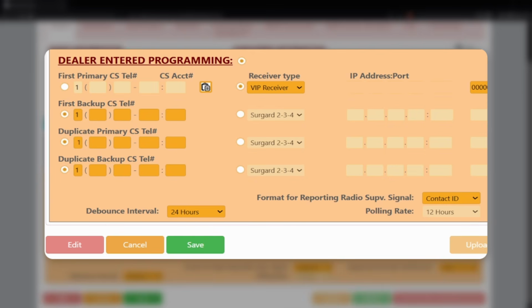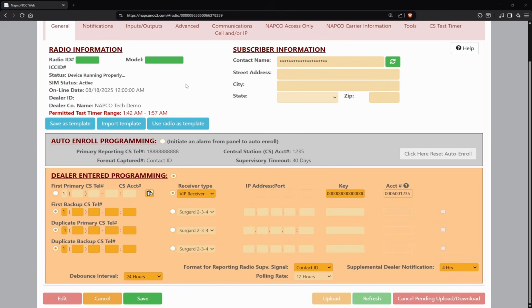When the radio fails to poll twice in a row, the receiver at the central station will generate a failure, and the failure will show with a signal code of YC. Some central stations don't show the actual code on their signal app, and instead will just show the text readout from their automation program. Sometimes it will show as a COM fail, and other central stations will have it programmed as a loss of central polling.